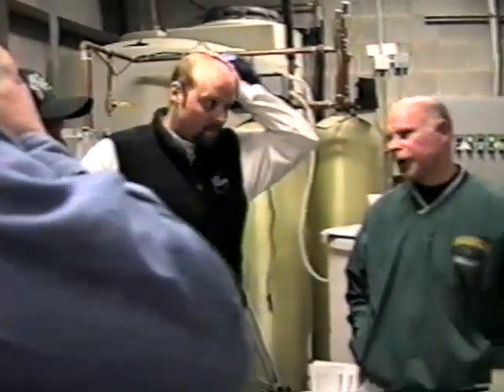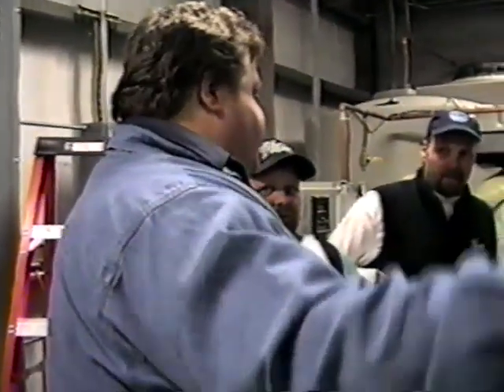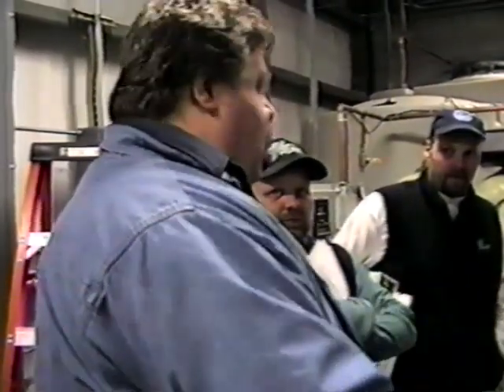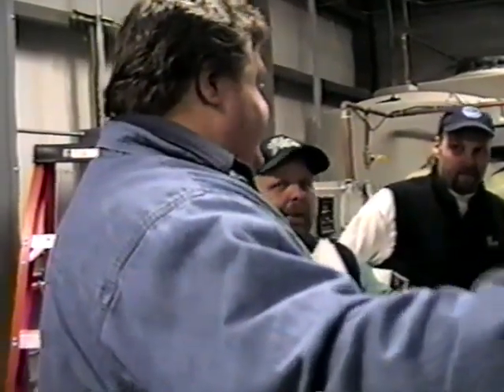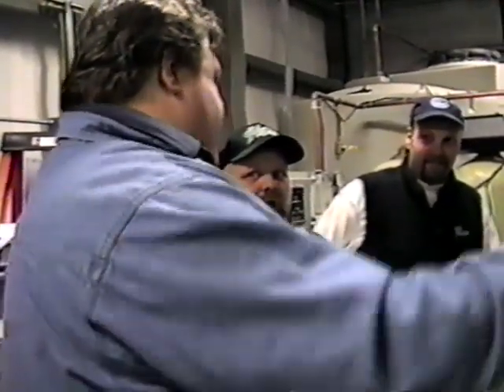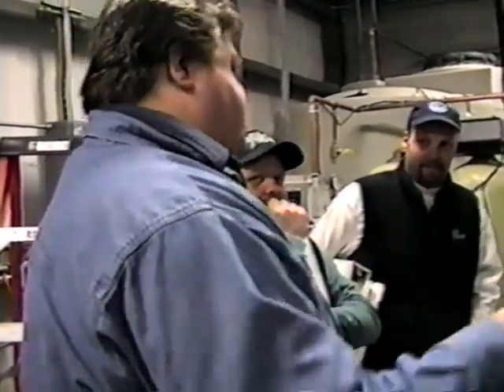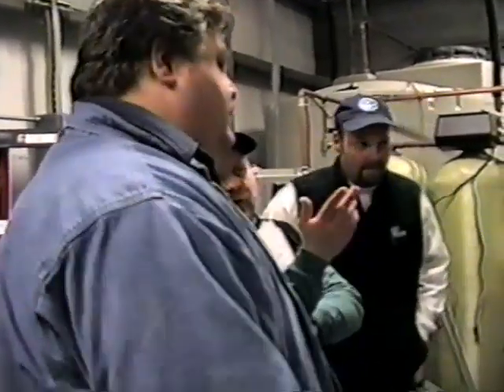But actually, the 45-55 is not the percentage you're supposed to run. That's the output of them. Right. They should run about 50-50, correct? Well, as far as capacity, what you're going to see on there when it says capacity, this will go all the way up to, let's say, 50%, and then this one will come on. So they should have actually done it capacity circuit A, capacity circuit B, as far as I'm concerned. But that's the way they've always done it. So if A never gets up to certain capacity, B would never turn on. Right. Maybe that's the thing.